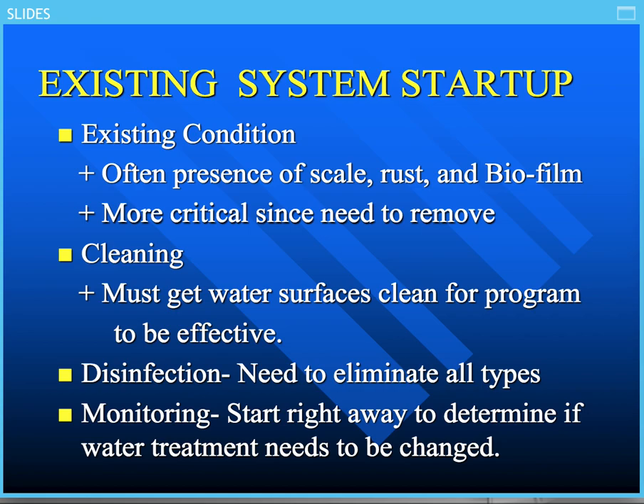Again, we're dealing with disinfection. Every existing system in your startup should be disinfected, because that is where we frequently find biological problems have occurred or are occurring, and the net result is that you're going to have corrosion problems and probably pathogenic material, microbes, present. So you must disinfect it with high dosage levels of chlorine or bromine, making sure it matches your treatment program. What are we trying to do? We're trying to minimize the potential for corrosion and for microbiological organisms that could cause fouling problems, corrosion problems, and microbiological pathogenic problems.